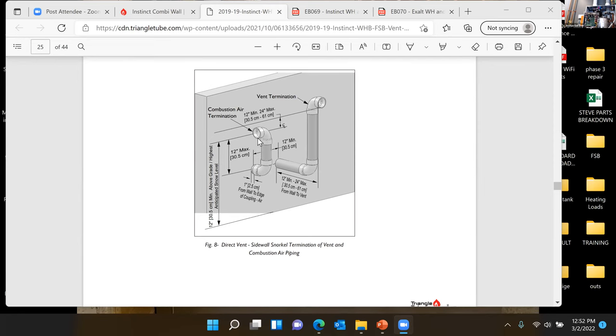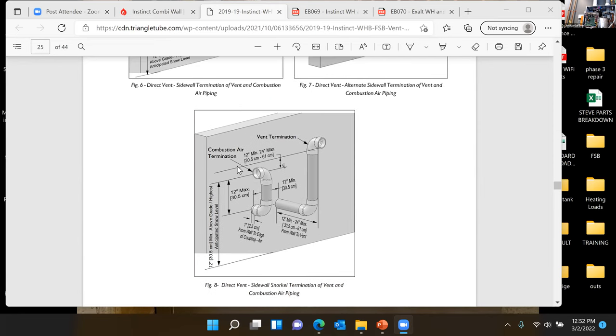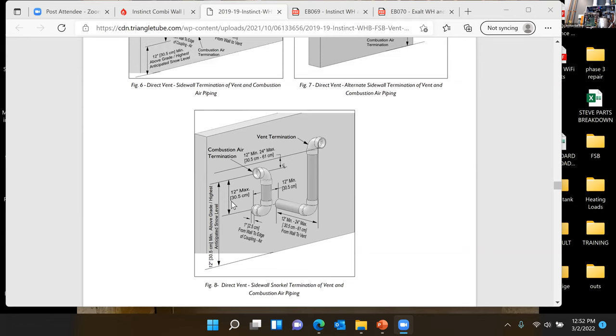In some installs, in some locations, we found that we were pulling in rain in here, and I'll show you on the teardown, but we have a piece of foam on the intake and we have our venturi. So if we have water coming in here, we can clog that up. We can have failed ignition issues. Or if we don't do our exhaust properly, we can cross-contaminate in really cold weather and bring that condensation in here. And then it comes directly into that venturi and just turns it into a big ice ball. And then we have no heat.